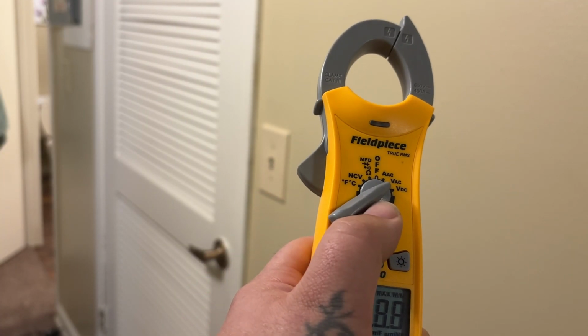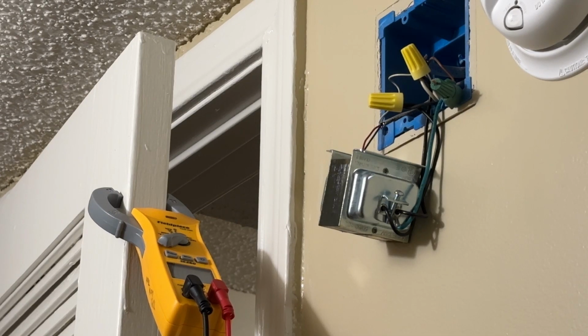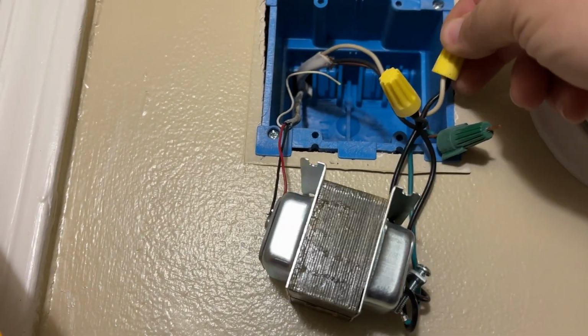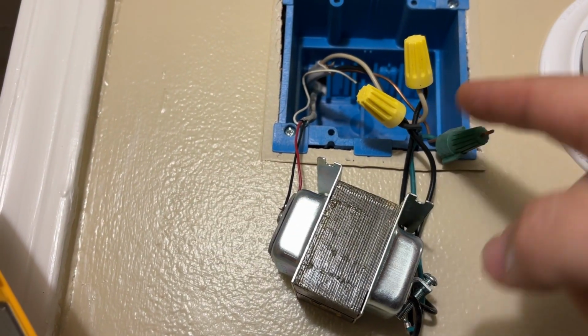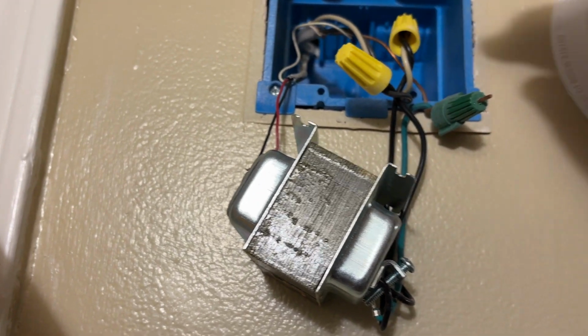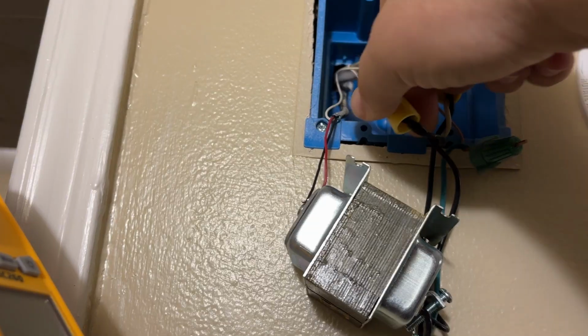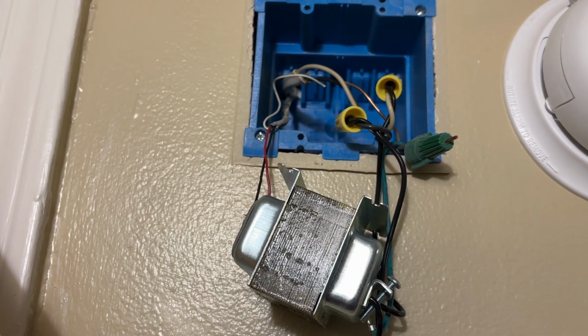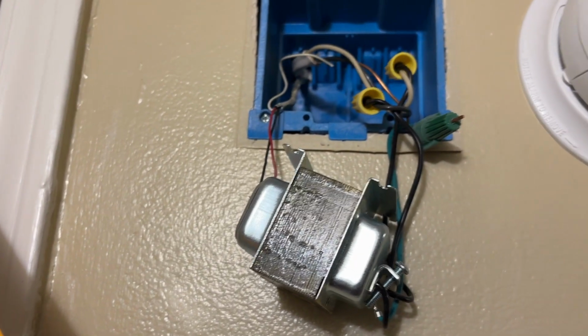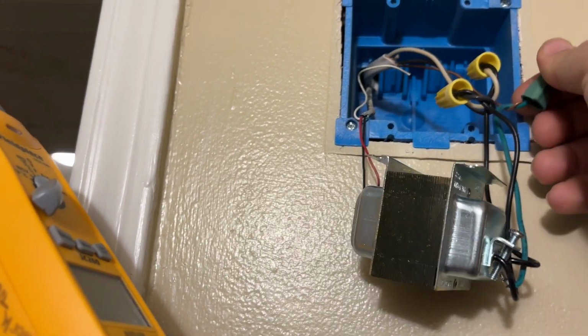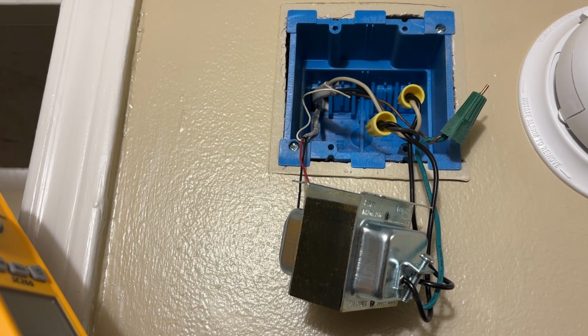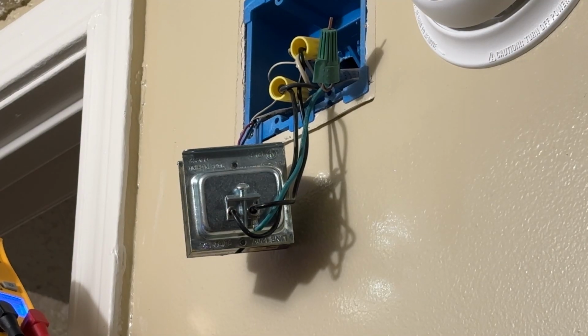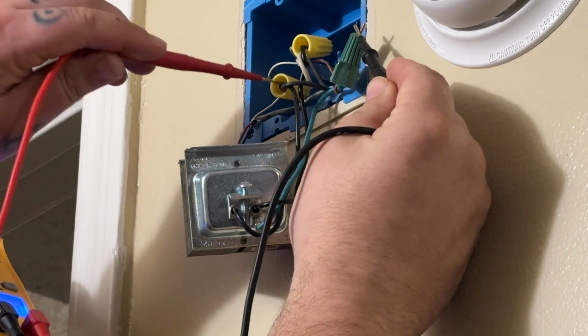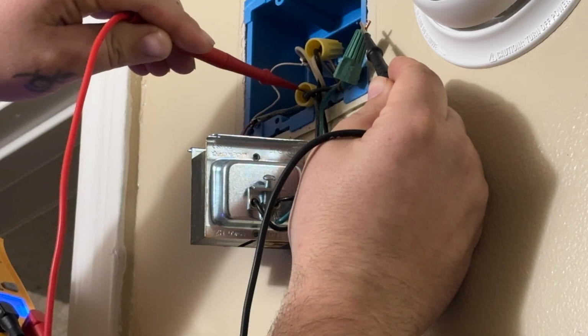Setting our multimeter to VAC. You can use the amp clamp to secure your multimeter to a door or something similar, or use the magnet on the back so you can have both hands to test these wires. Find your neutral white and your line coming from the breaker. Take your wire nuts and fold them back at an angle away from you to where you can see the inside of the wire nut. This will give you a place to test your multimeter without having to remove the wire nuts. Using the red lead of our multimeter and the black lead of our multimeter, our black we can go to ground. Our red will go in the wire nut, ensuring we get a proper connection, and we'll verify we're getting 120 volts.